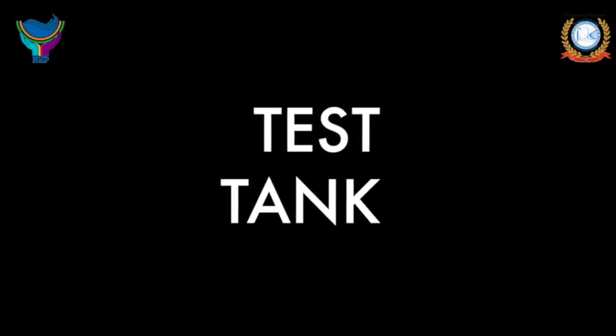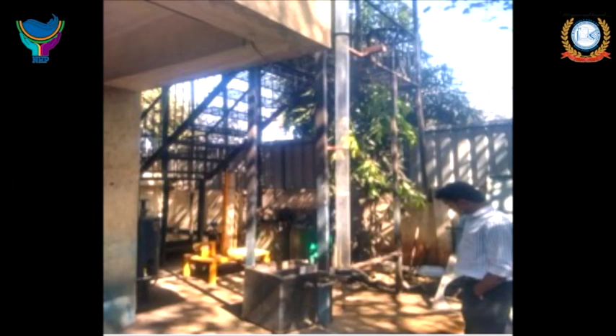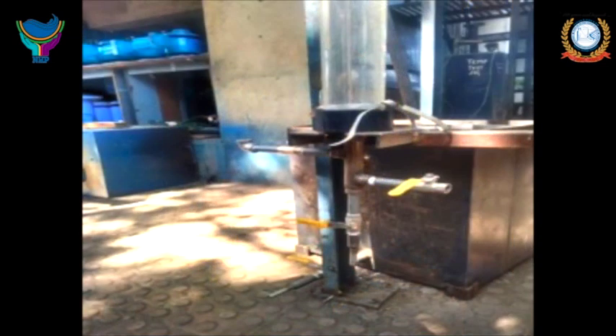The test tank. The sensors can be checked in a transparent tank which is used to test the response of the sensors by varying water levels in the tank with a scale for visual observations. Performance of the sensor will be observed by placing the pre-calibrated master sensor and the sensor that is to be tested at the bottom of the tank and varying the water column up and down gradually with small increments.